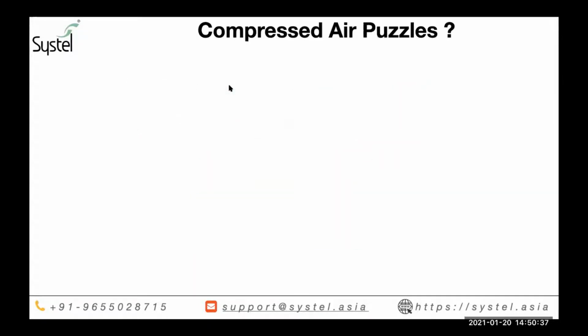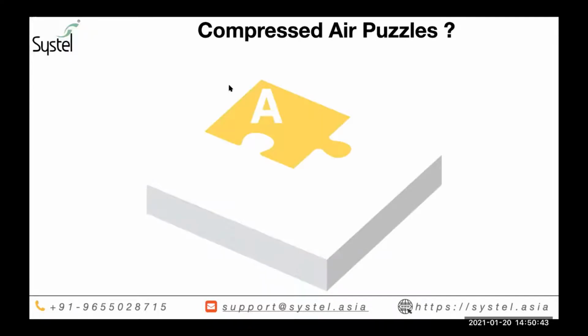Given this, I've broadly classified some of the puzzles that come into managing a compressor system. The first one is how much air is actually produced. This is a debatable subject, since there is a big misunderstanding between the end user's perspective of the compressor's rated capacity and the manufacturer's perspective. When you procure a compressor of 1,000 CFM capacity, the end user usually assumes that 1,000 CFM is going to be pumped into the facility, into the pipelines.